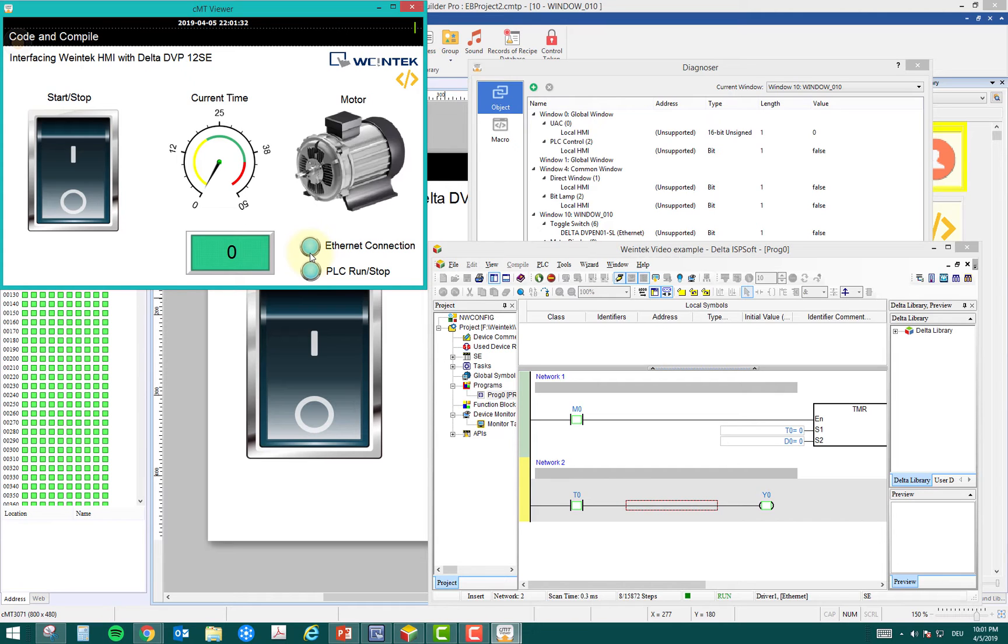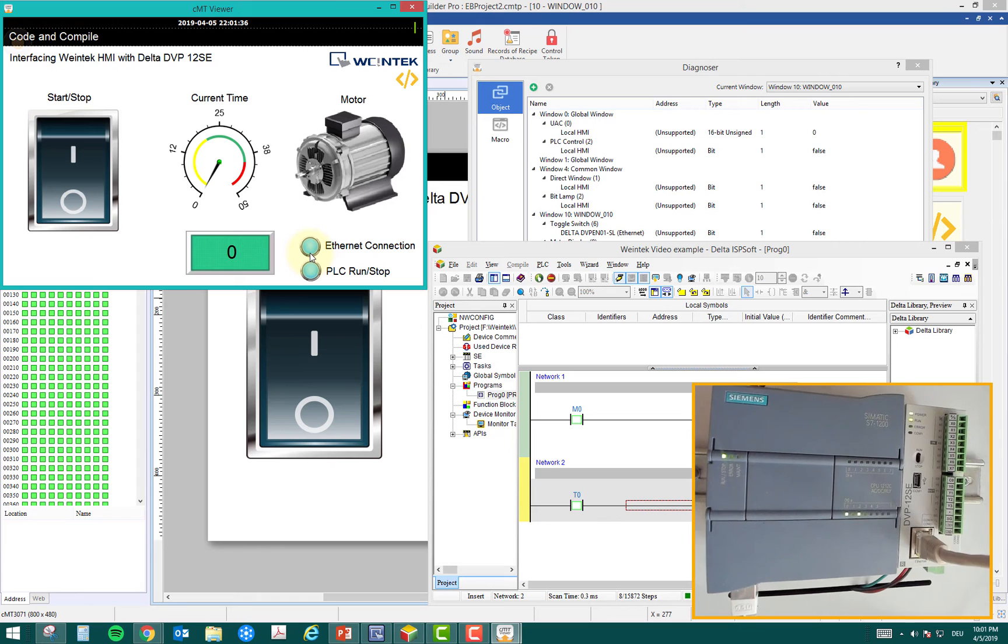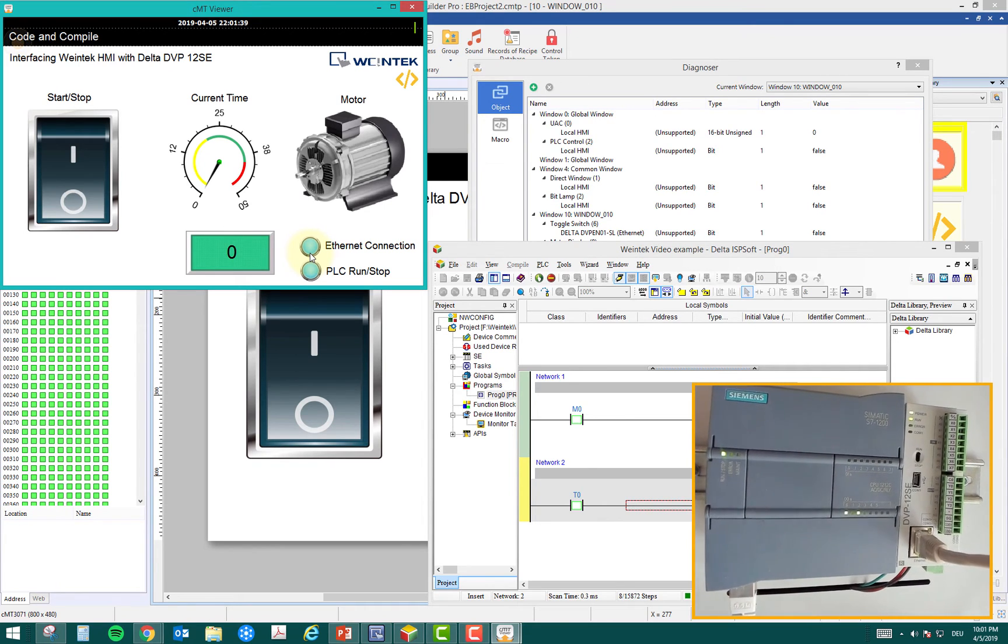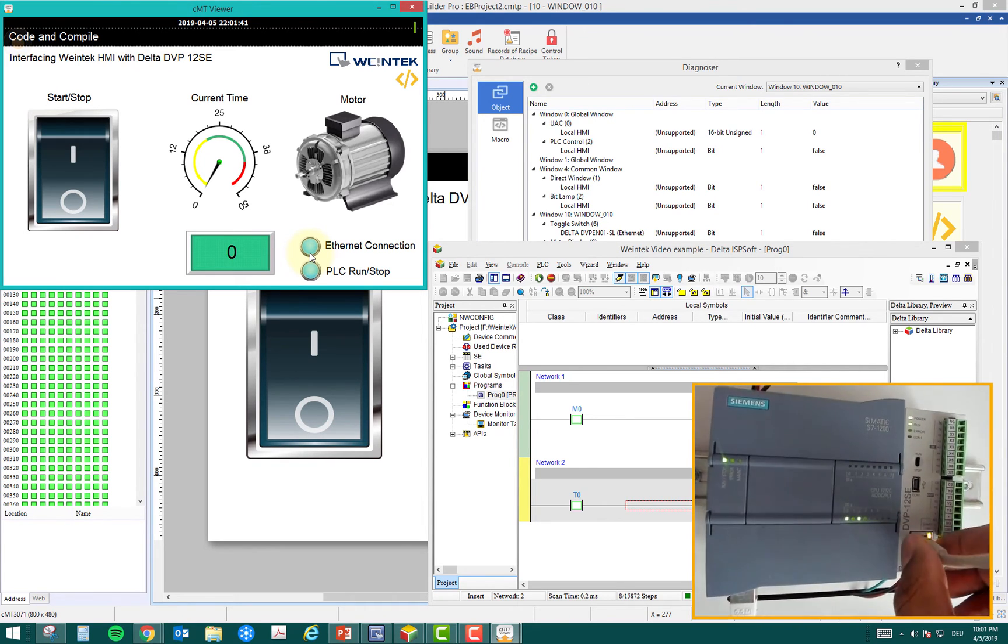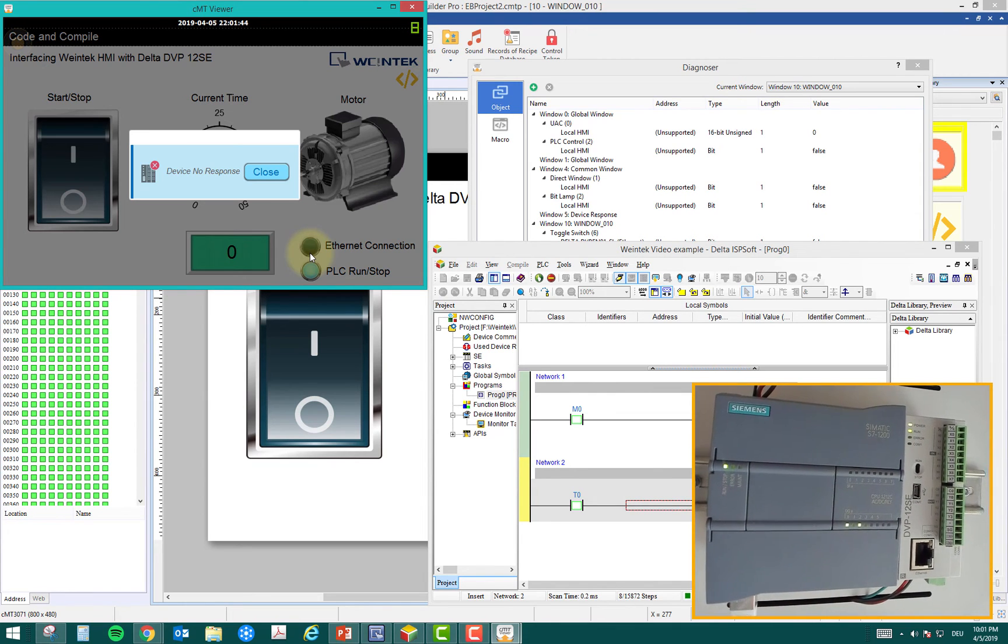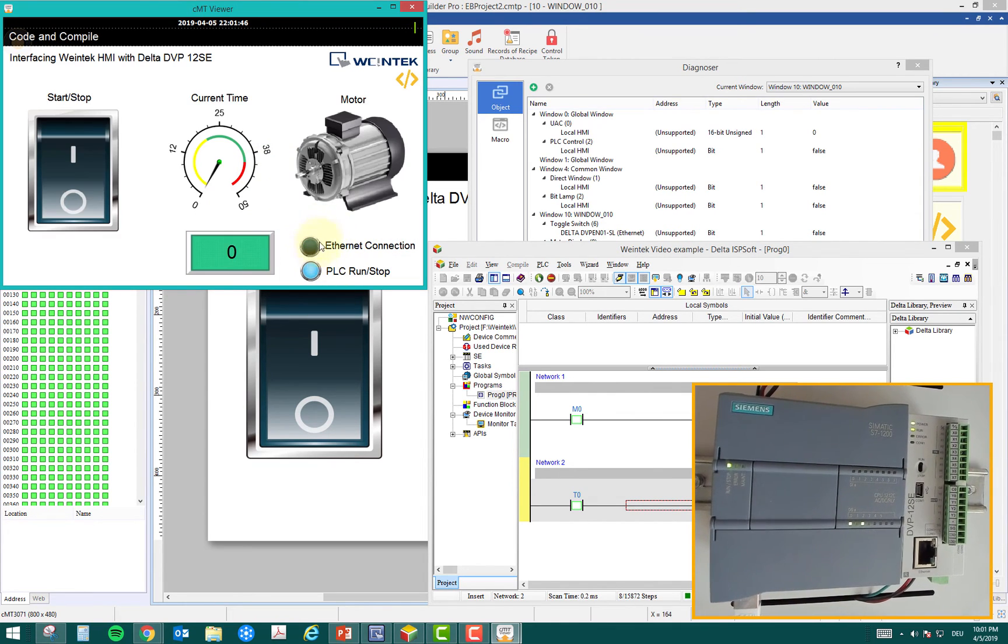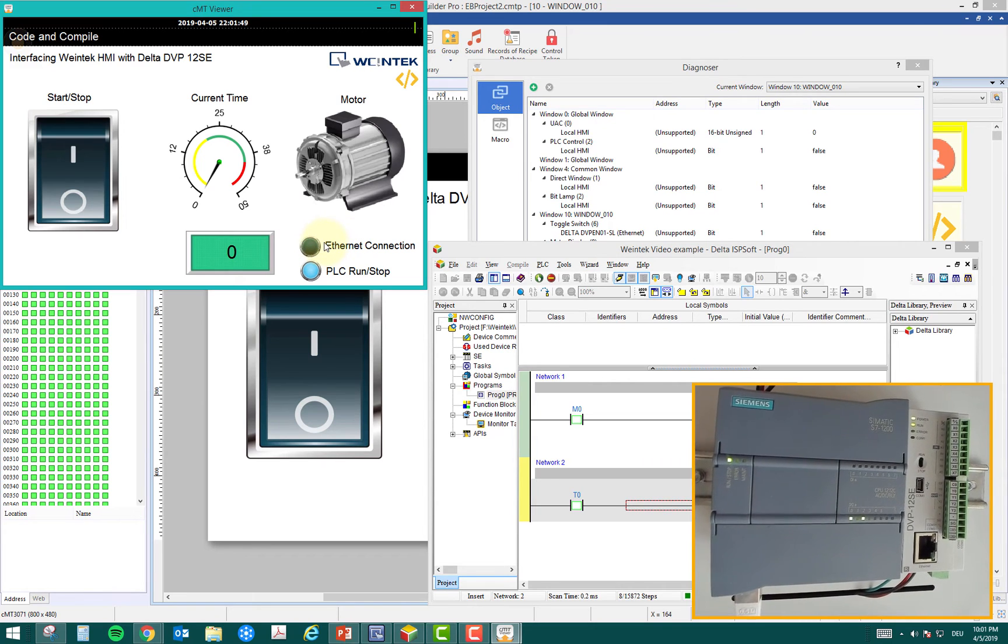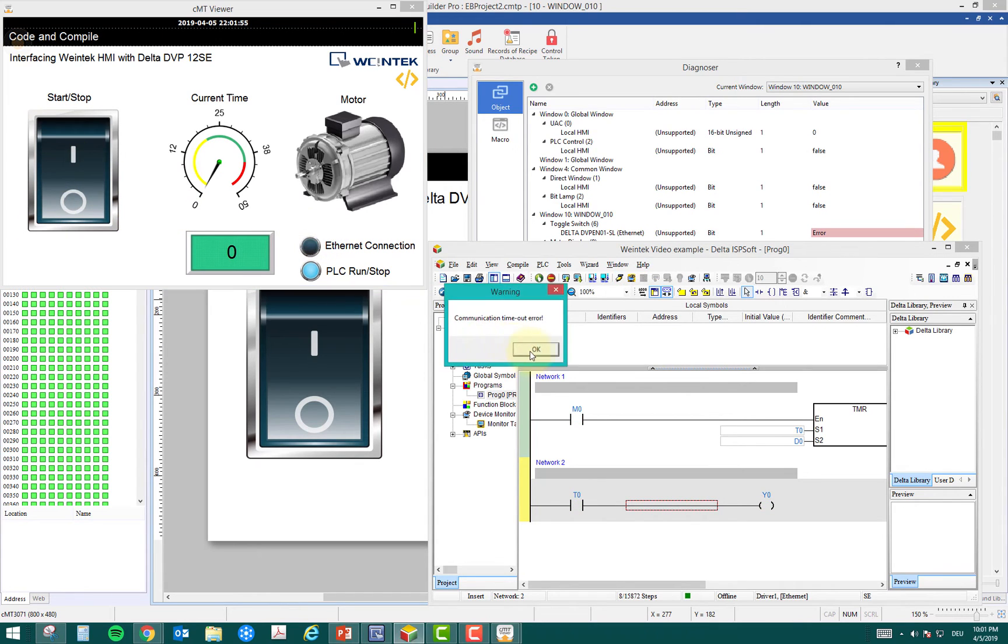I'm just going to unplug the PLC ethernet port and we'll see the status here. I just unplugged my ethernet connection and you can see that the ethernet bit is off. You don't know what could be the problem with the communication, but the communication is not running at the moment. This will also show you the status about the connection between the PLC and HMI.